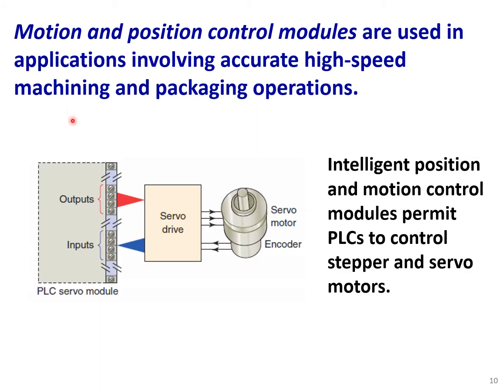Motion and position control modules are used in applications involving accurate high-speed machining and packaging operations. They are similar to PID modules but specifically designed for motion or position control. They accept encoder data and interface with a servo drive. They are a very specific type of PLC module designed for motion or position control.